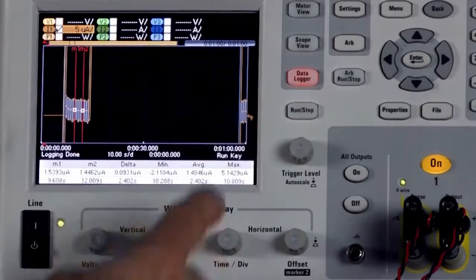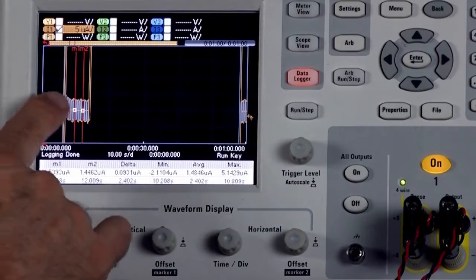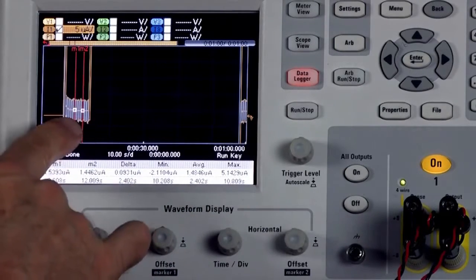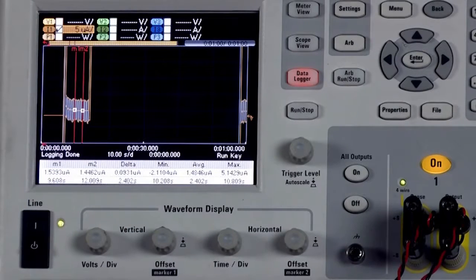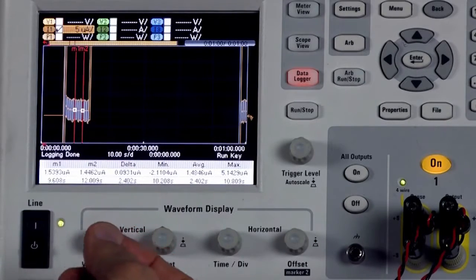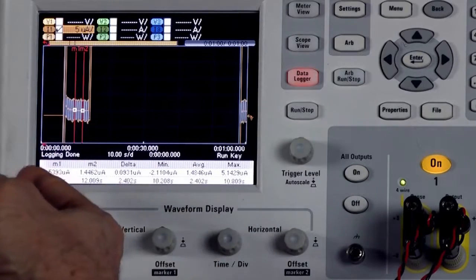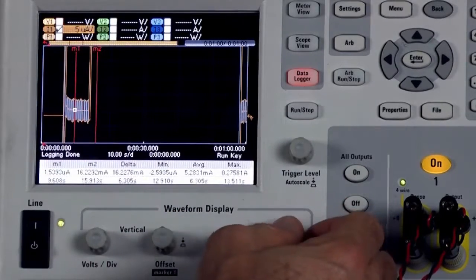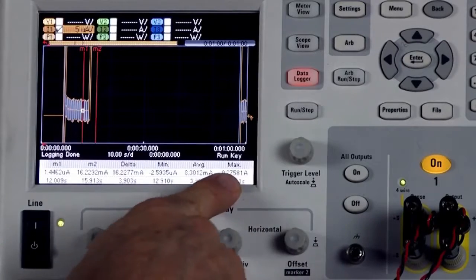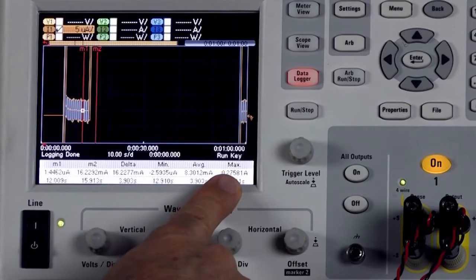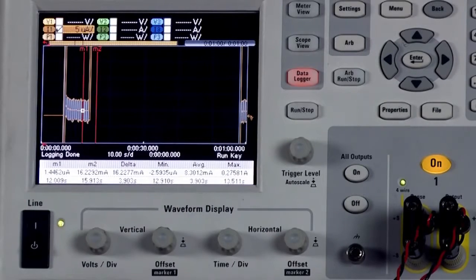But if I turn the markers back on, you can see that the noise level is probably about not quite 10 microamps, so maybe 8 microamps of peak-to-peak noise. So we're able to resolve down to maybe tens of microamps at this low level, as well as capture the peak. And I've moved these markers over again. You can see we're still measuring this peak at 275 milliamps. So this is really the value of this SMU with its seamless ranging, and allows medical device designers to look at the dynamic characteristics of their medical device and understand how this will deplete the battery.